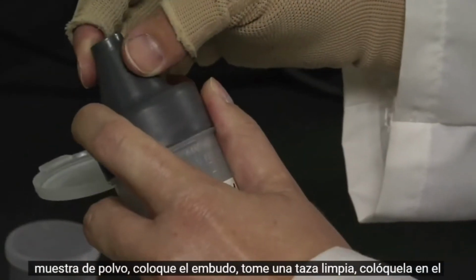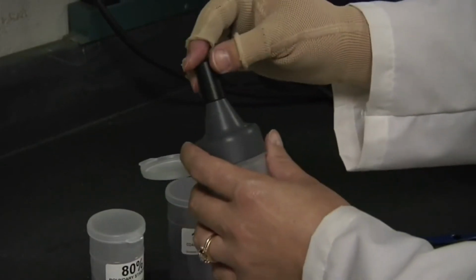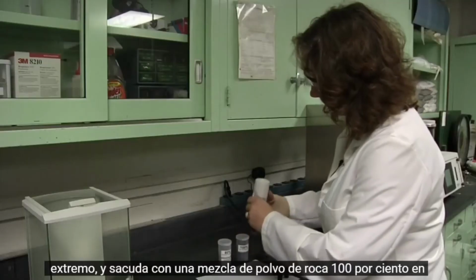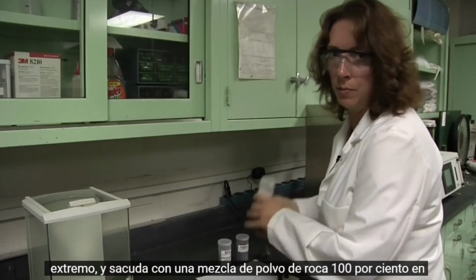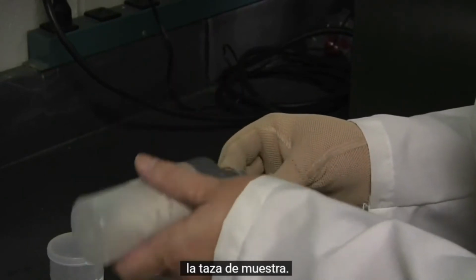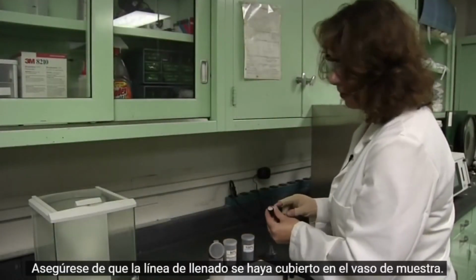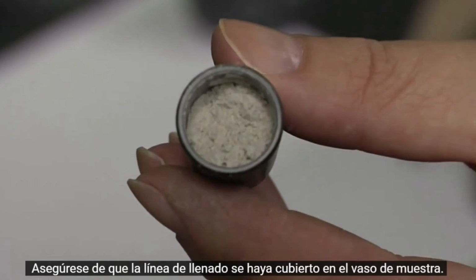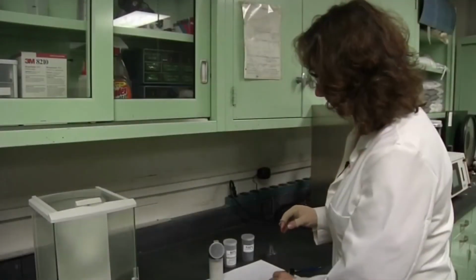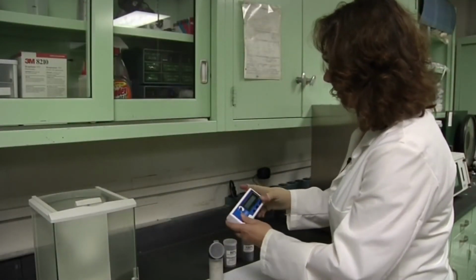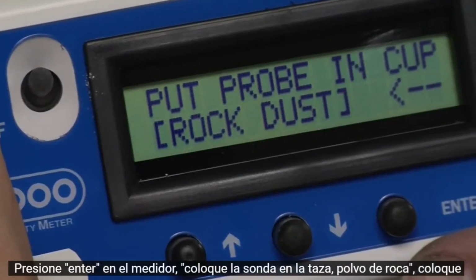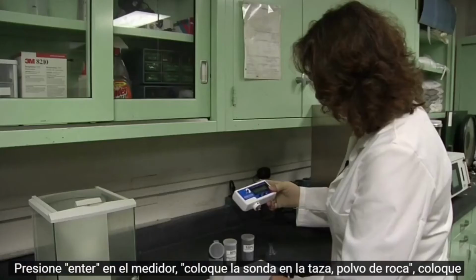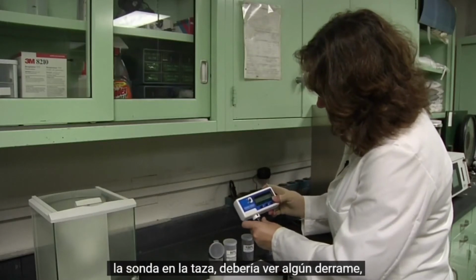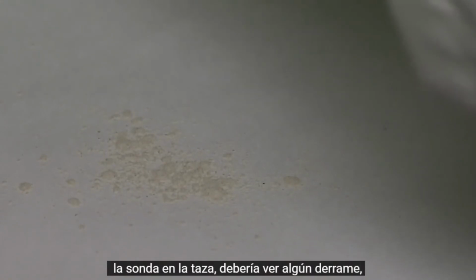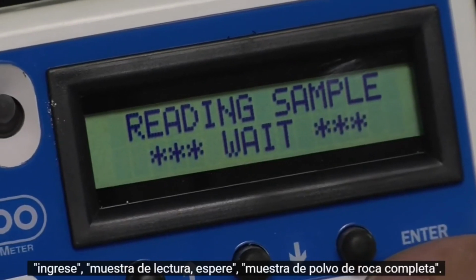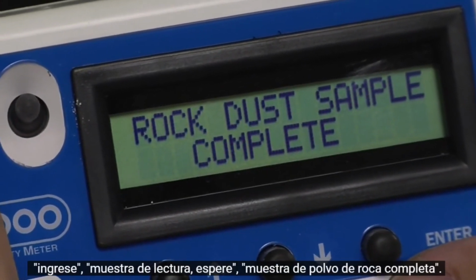attach the funnel, take a clean cup, put it on the end, and shake out a 100% rock dust mixture into the sample cup. Make sure the fill line has been covered in the sample cup. Press enter on the meter. Put probe in cup, rock dust. Put the probe into the cup. You should see some spillage. Enter. Reading sample, wait, rock dust sample complete.